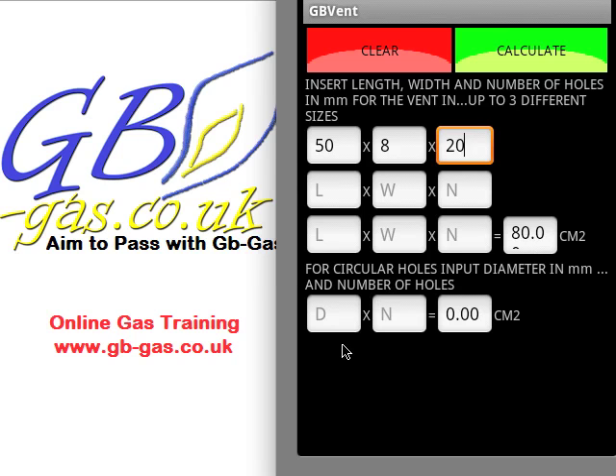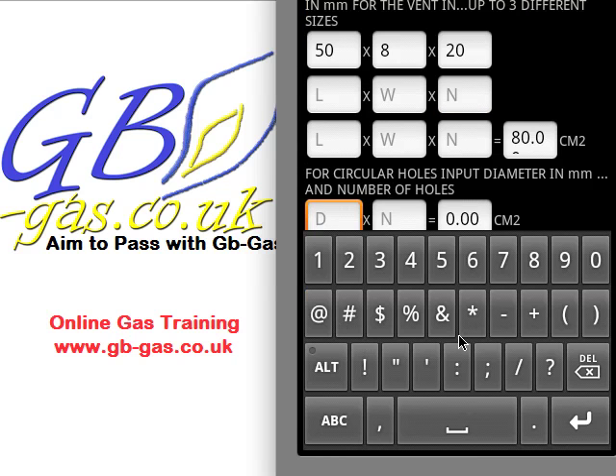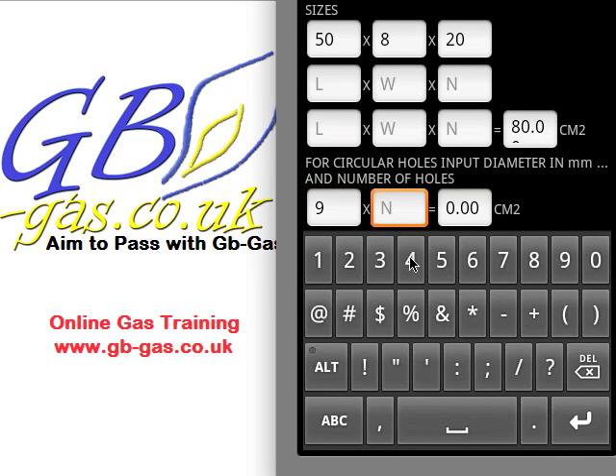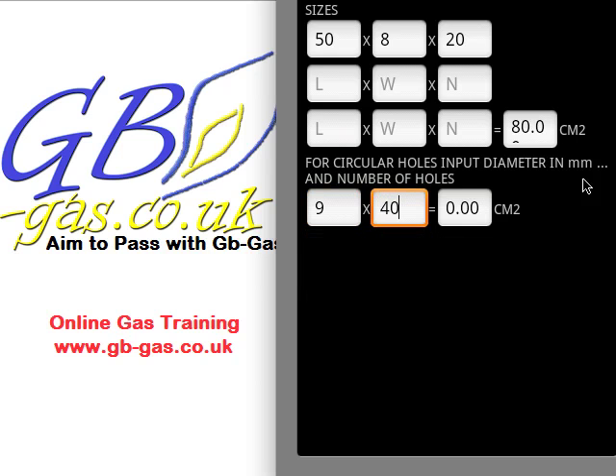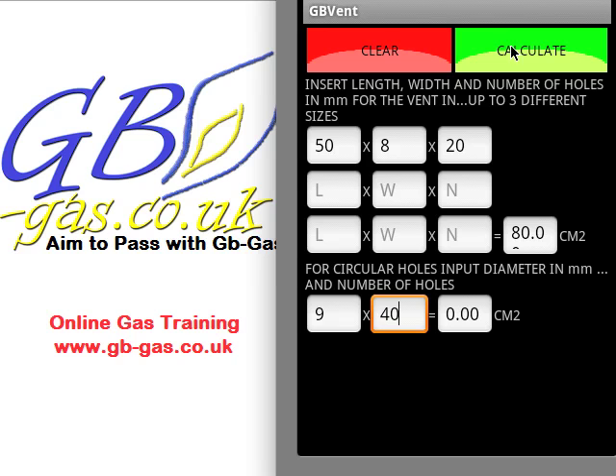We can also do the same for circular holes. We put in the diameter of the hole — that's the full distance across — and again this should be between 5 and 10 mm, so let's put in 9 mm. Let's say there are 40 holes at 9 mm in diameter. Pressing the back button gets rid of the keyboard, and then we hit calculate. That ventilator would be equivalent to 25.4 cm².